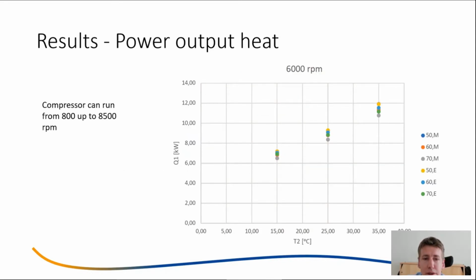If we speed up the compressor a bit to 6000, then we'll have an output between 7 and 11, something like that. I should say that this was done between 2000 and 6000 RPM. The compressor itself is actually able to run between 800 and 8500 RPM. So there is a very, very large range that is possible to run in. But this also puts a lot of pressure on all components, and especially the expansion valve.